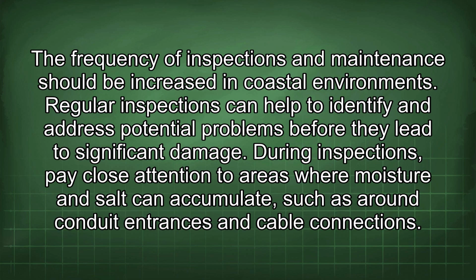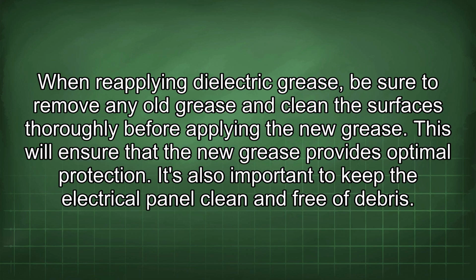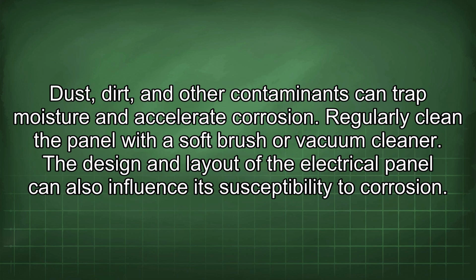During inspections, pay close attention to areas where moisture and salt can accumulate, such as around conduit entrances and cable connections. When reapplying dielectric grease, be sure to remove any old grease and clean the surfaces thoroughly before applying the new grease. This will ensure that the new grease provides optimal protection. It's also important to keep the electrical panel clean and free of debris. Dust, dirt, and other contaminants can trap moisture and accelerate corrosion. Regularly clean the panel with a soft brush or vacuum cleaner.